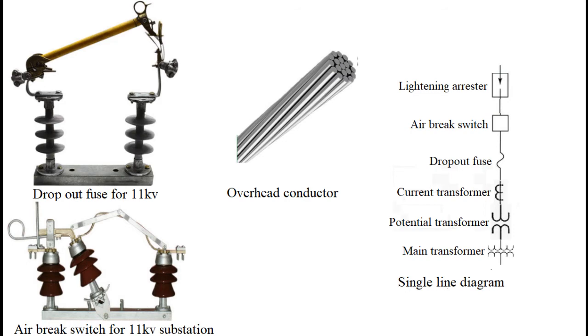One another element that needs to be inserted in the circuit is fuses. In case of an 11 kV substation line, these are known as dropout fuses. For simplicity and to keep equipment dead for maintenance purpose, we will choose to keep the switch at the very beginning of our substation. Dropout fuses for each phase shall be installed at the beginning of the substation. Therefore, pin insulators at the top of the first pair of poles are not necessary. The lightning arrestor would be before this switch.